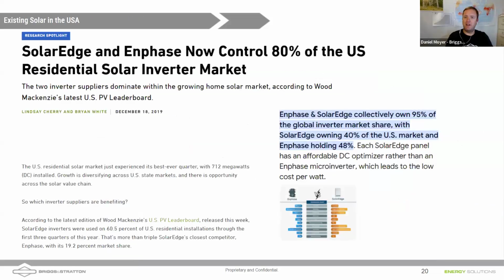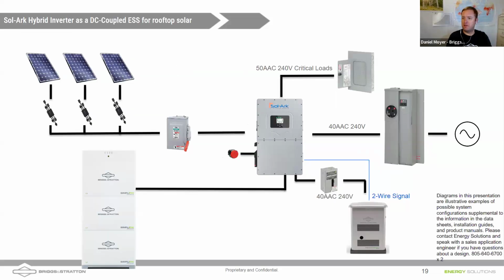So one comment. I know, Nathan, go back one slide. I know we're coming up halfway through, but you show a 40 amp breaker going to that. I assume that's a 200 amp, 200 bus main load center there. We're showing 50 amps of loads that were supposed to be critical, and a 60 amp for that solar. And why can we now put a 60, right? The 120% rule isn't really a factor anymore. Why? Because these inverters now have power control systems, right? They can still draw 60 amps off of that main panel, but they're never going to send back more than what you program it to.